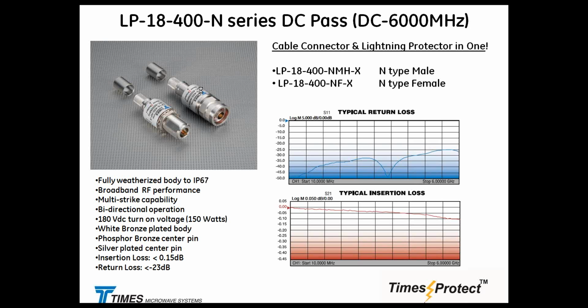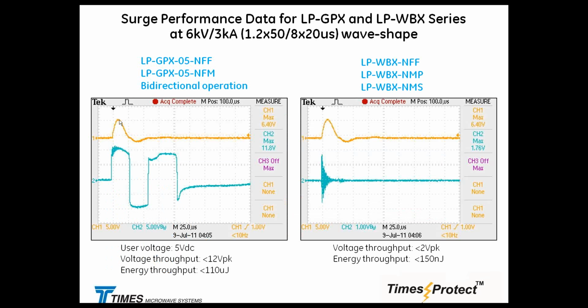Surge testing. It is very important that the manufacturer provides you with the data. This is the current trace, and you are looking right now at 6.4, so that would be like 3,200 amperes going into the device, and this is the corresponding voltage. So as I said, every protector has to be designed to withstand a given amount of current, which is advertised, and hold the differential voltage between the center pin.